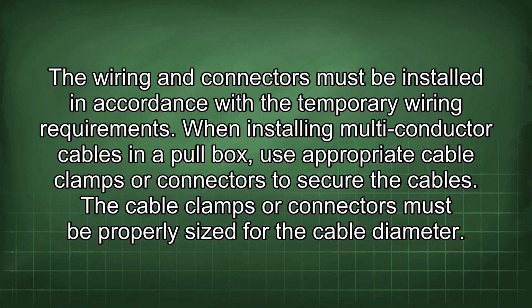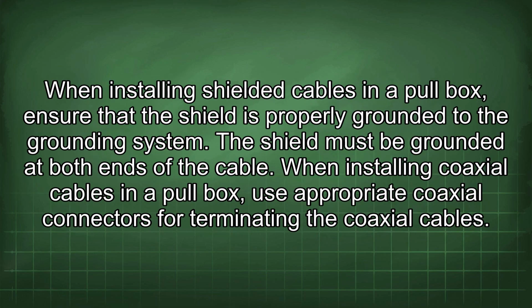When installing multi-conductor cables in a pull box, use appropriate cable clamps or connectors to secure the cables. The cable clamps or connectors must be properly sized for the cable diameter. When installing shielded cables in a pull box, ensure that the shield is properly grounded to the grounding system. The shield must be grounded at both ends of the cable.